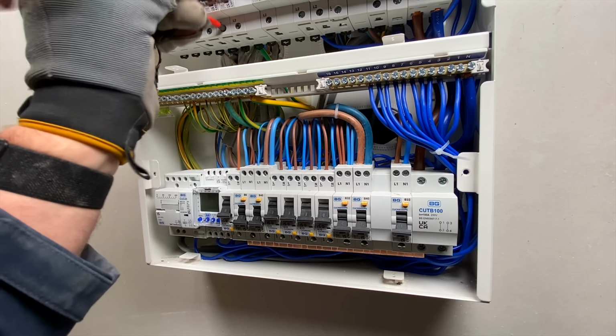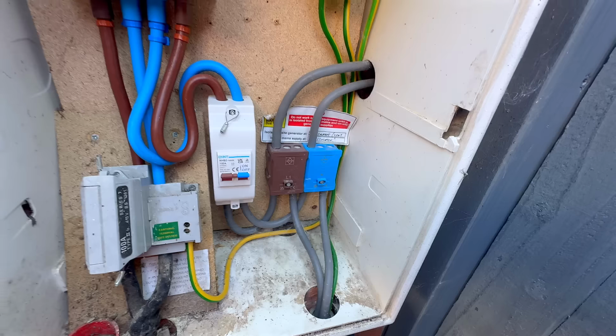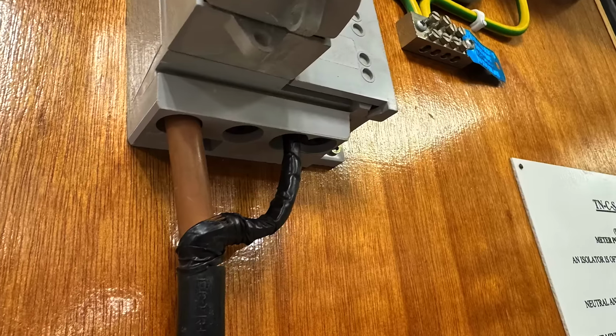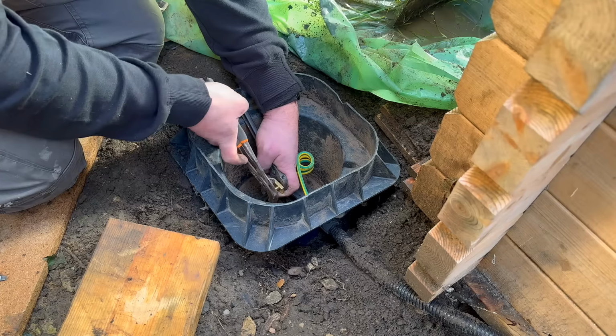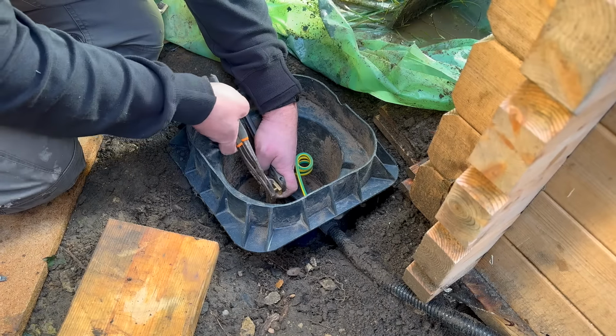The supply to this office is taken from the main installation, which is a TNCS system. And providing that earth remains effective, BS7671 does not require us to install a separate earth electrode for this installation. So exporting the PME in this situation is permitted. Now adding one here does not make this installation automatically safer, but it would make this video a whole lot duller as I need to show you how to test one, apparently.